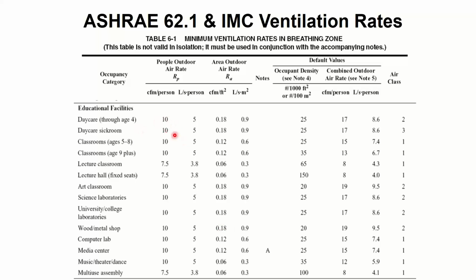So when we look at some of the typical spaces, this is K through 12 in this audience. So you're looking at classrooms, ages 5. Well, actually, both classrooms are the same nowadays. So you need 10 CFM per person plus 0.12 CFM per square foot, and you add those two numbers together. If you have something like art rooms and science labs and stuff like that, the per person number stays the same, but the per square footage number goes up because you're going to have other stuff going on. You're going to have paints and acetone and whatever's going on in the art classroom and the science lab. God knows what you're going to have in there. If you have wood and metal shops, same thing, 10 per person, but a higher, beefier rate for the equipment that you're using, right? Maybe you got a grinder or maybe it's welding or something like that. So you have more exhaust requirements, hence more fresh air requirements in this space.